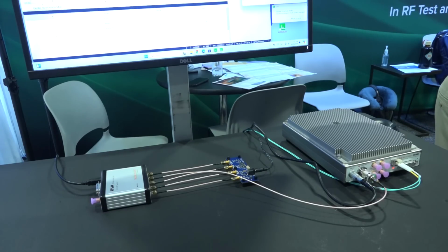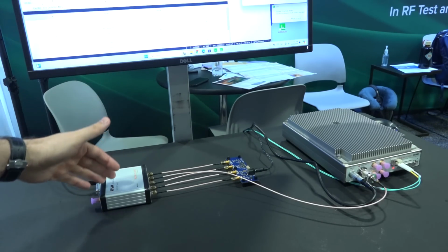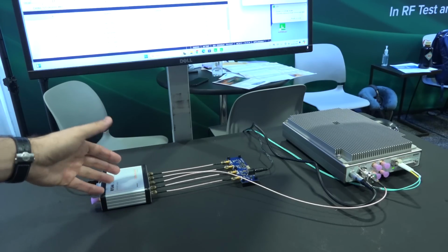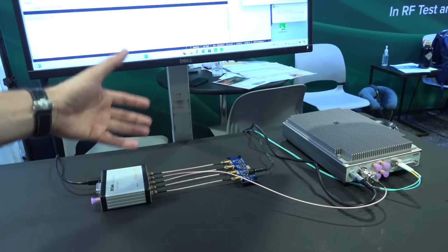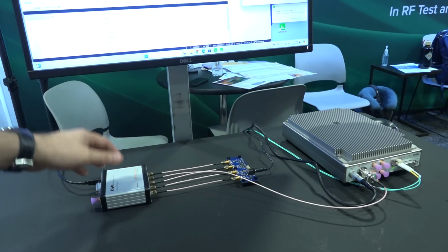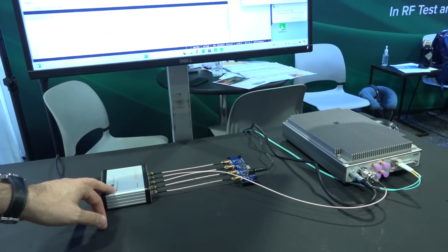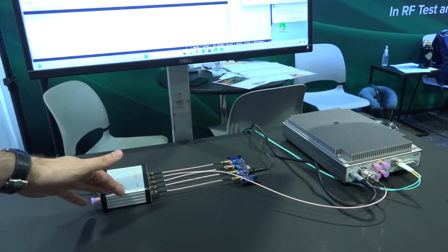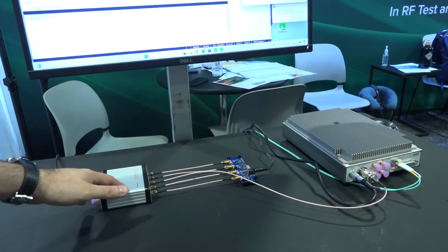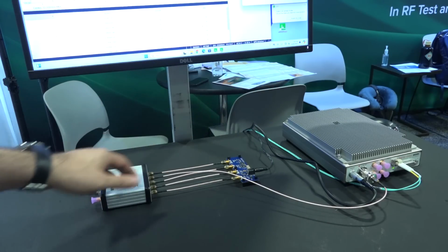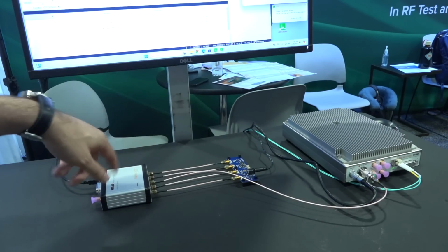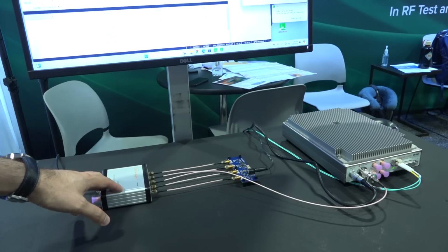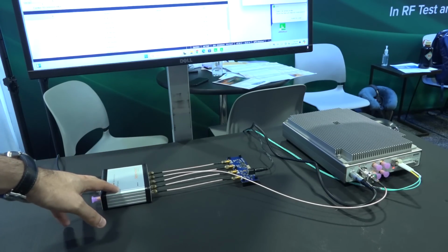And here in this station, we're taking advantage of the API interfaces of the Spike software that's already available with various switch control capabilities and support built in there, so you can start running your own script and create an automated test setup. This is an example of this just to demonstrate the idea, but the Spike software itself, because it does have that open API, you can essentially write anything you want and connect it to any combination of these devices that you want and synchronize them. But being able to do this in kind of a support directly from the manufacturer allows you to now expand automated testing using their ever-growing set of equipment.